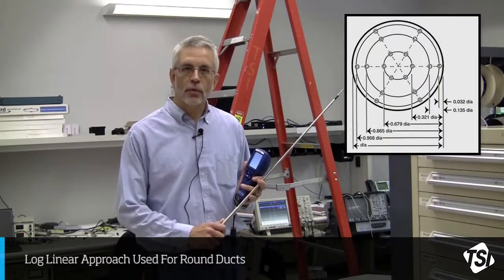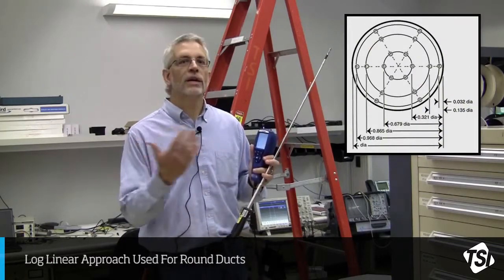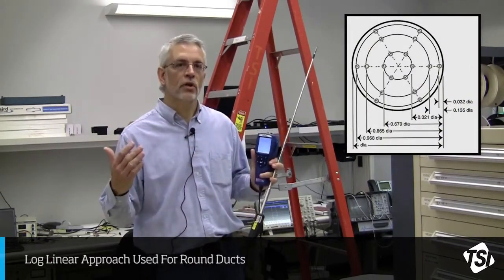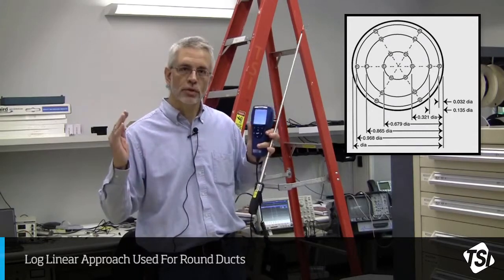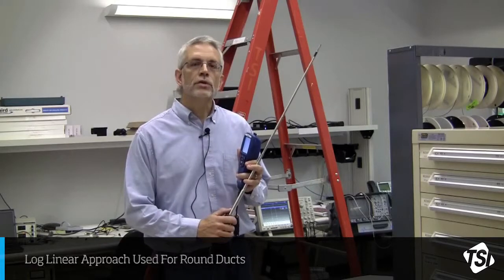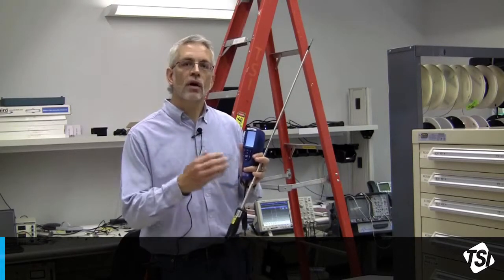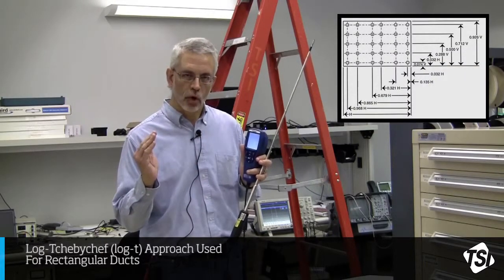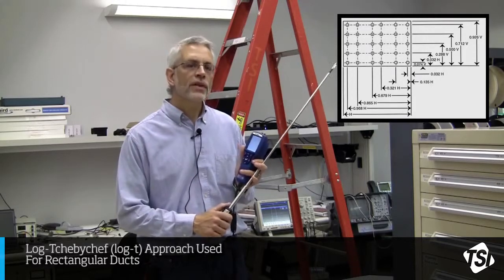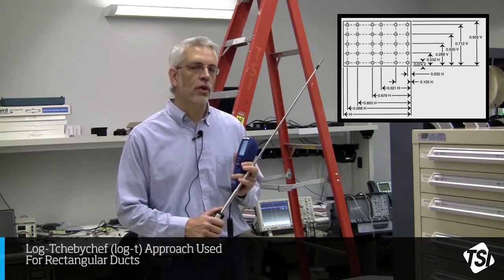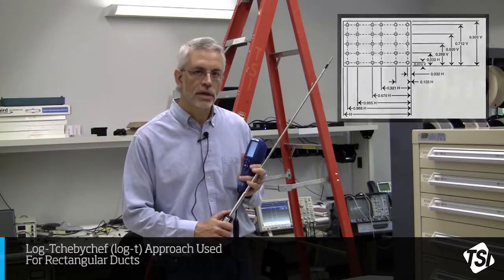Secondly, as we mentioned before, the flow within a duct is not necessarily uniform or even across the duct. Usually it slows down near the duct wall. So it's important to use a technique that will account for that slower flow near the walls. That technique for a rectangular duct is called the log-Chebyshev or log-T approach.